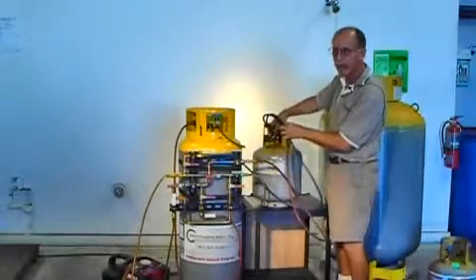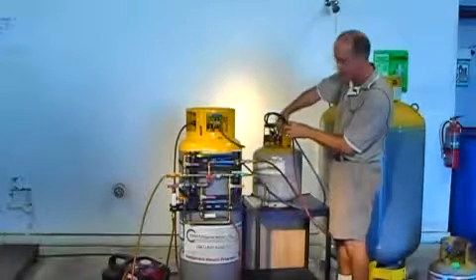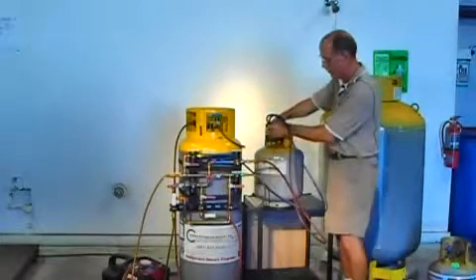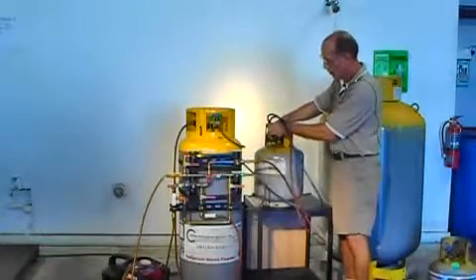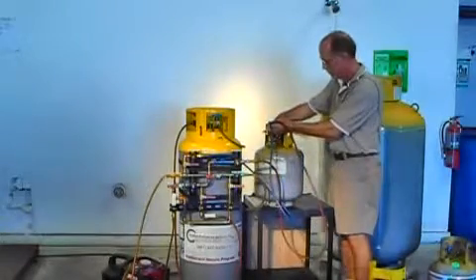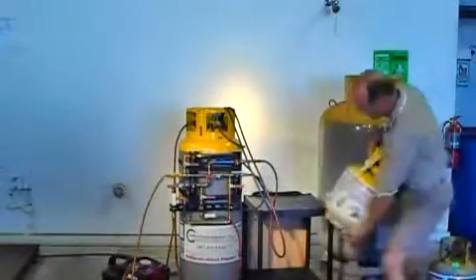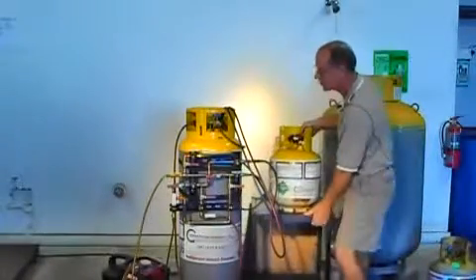We have pulled this into a vacuum but before it goes back into service we'd suggest that you put it on a vacuum pump and know that you've pulled it down into a good micron vacuum before we put it back in service. So we'll disconnect these. We haven't lost one ounce of refrigerant. Let's put this bad boy up there. 80 pounds. Oh there you go. Somebody really did a good job of filling this one up.